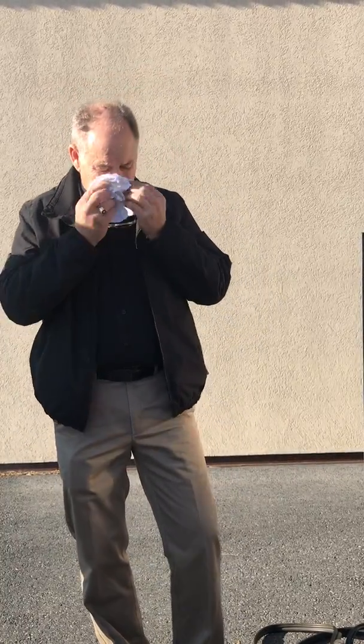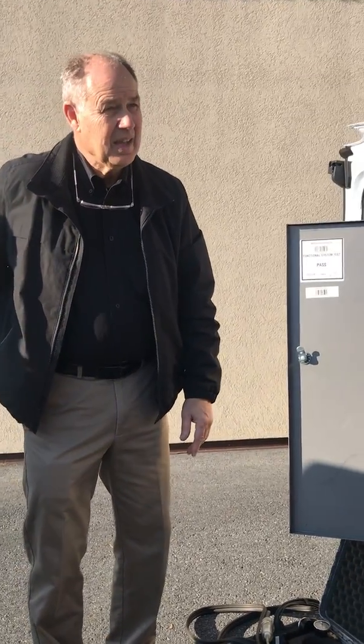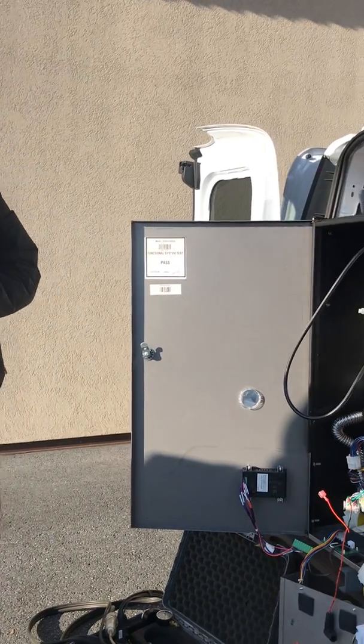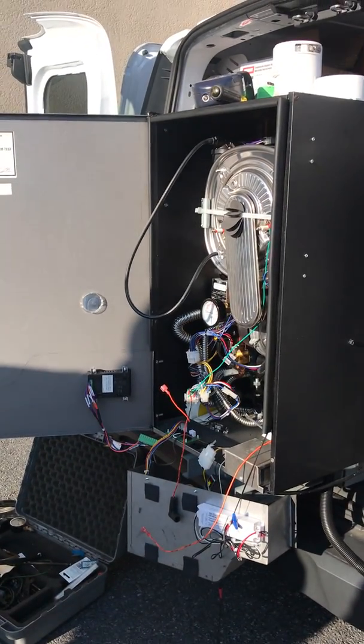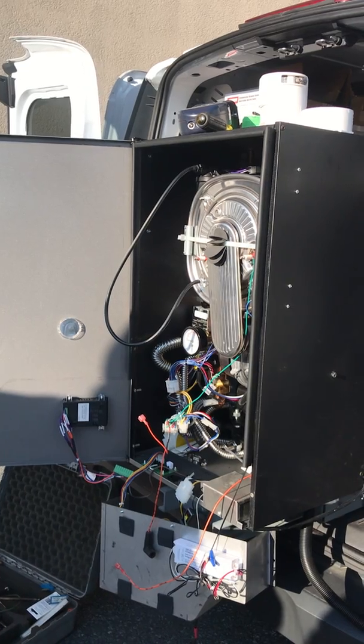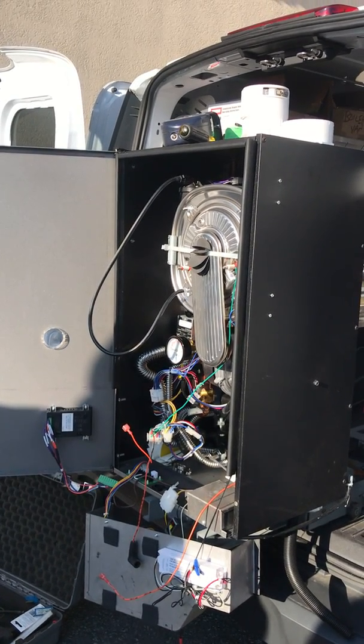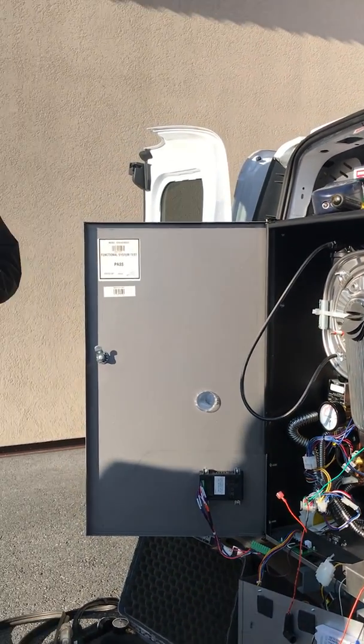So guys, while we're out here still on this, anything from the standpoint of diagnostic or service that we've run into that we have to review? We get a lot that make a whistling sound. Okay, whistling sound, especially if you go to propane. Yes, they're all on propane, on ignition. Okay, there's an adjustment, and we'll show you. I've got two boards. We're going to go from the lowest we can set our ignition speed to the highest. You usually get it on short terminations where you're coming up and going right straight out.